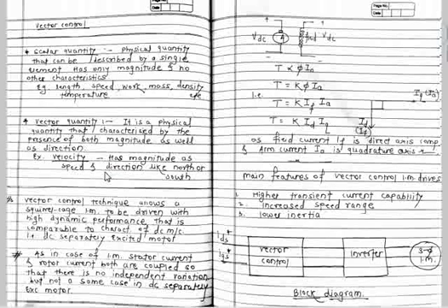So we can say that there is no decoupling between the torque and the speed, meaning torque and the flux. So such kind of speed control or torque control is not suitable where there is a very dynamic change in the load pattern. Obviously, such a motor control will give you a sluggish response. So this variation basically gives a sluggish response in case of the torque as well as the speed.